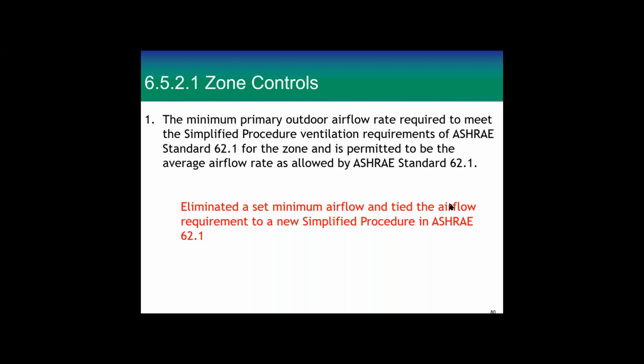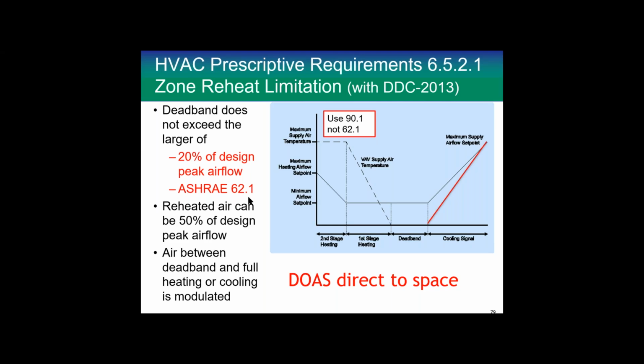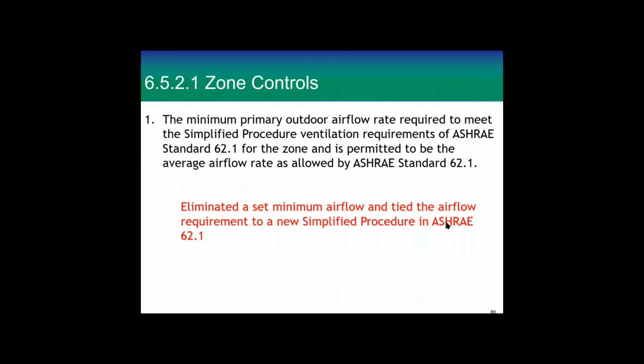So the minimum primary airflow rate required to meet a simplified procedure ventilation requirement of ASHRAE 62. ASHRAE 62 came out with a new simplified procedure, I think it was 2019, and you can use that. So when we adopted that, we eliminated a minimum set airflow and tied the airflow requirement to the new simplified procedure, ASHRAE 62. So the 20 is still available to you to think about, but officially, that's what we mean by ASHRAE 62 now: ASHRAE 62 by the simplified procedure.